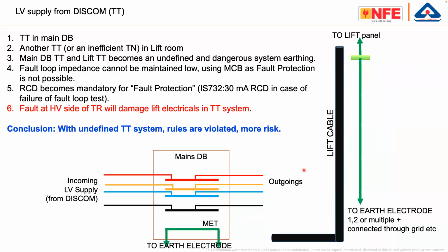But what we do is, for example, the main panels are connected to a separate earth electrode. The lift panel is connected to a separate earth electrode. Thereby, we make our installation highly unreliable. As in point number 6, a fault at the HV side of the transformer will damage lift electricals in a TT system. So these are the points which we are supposed to discuss.